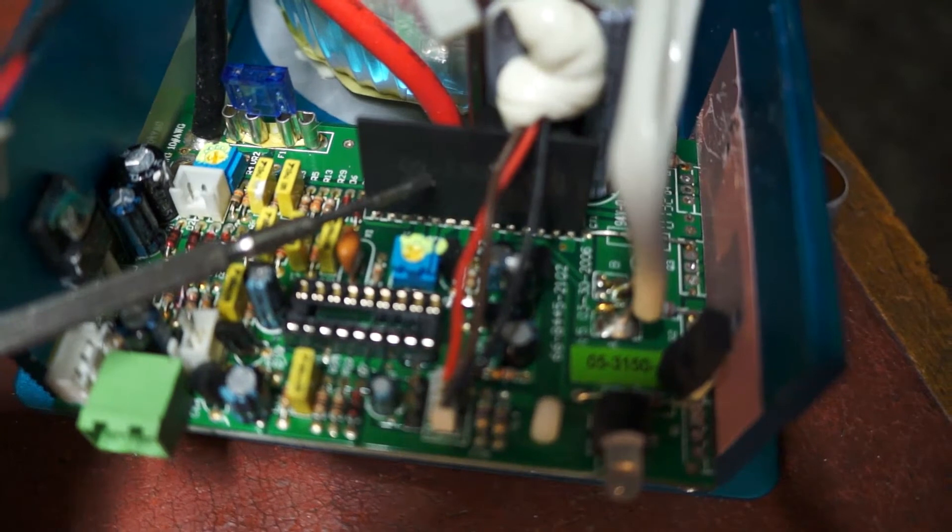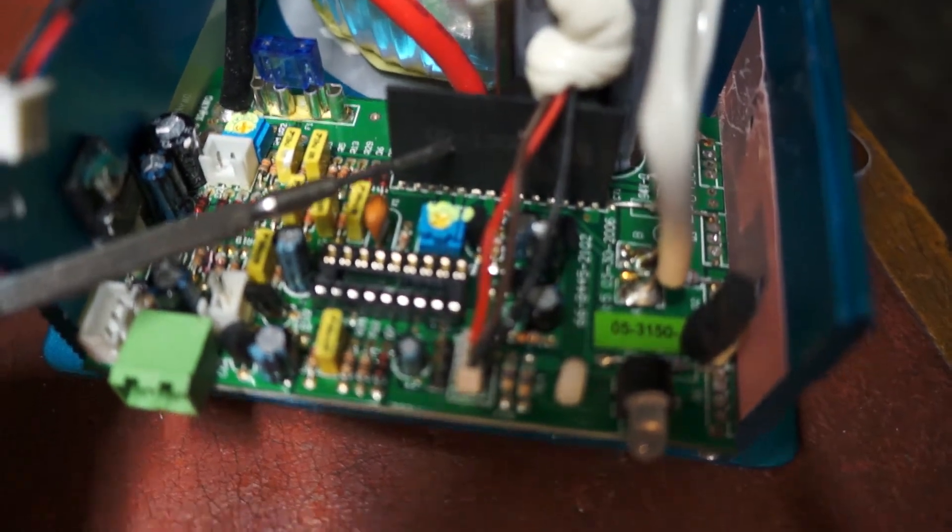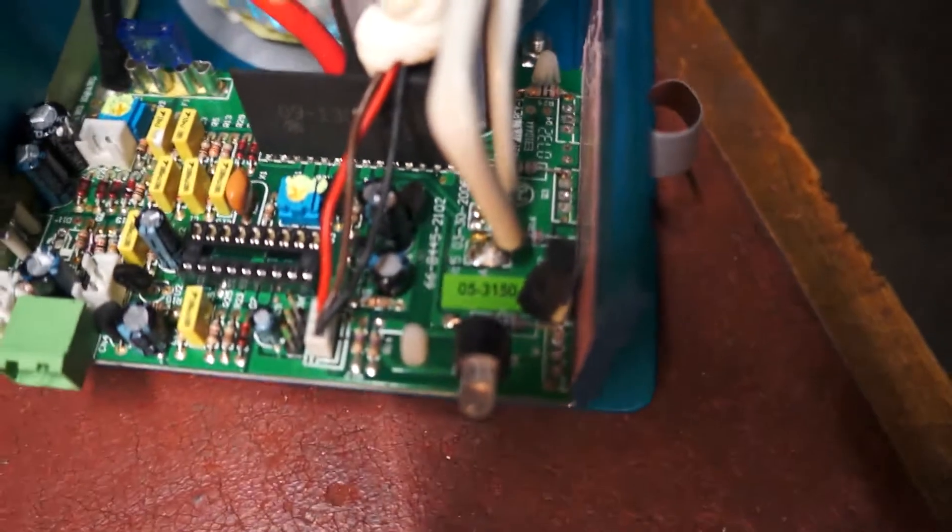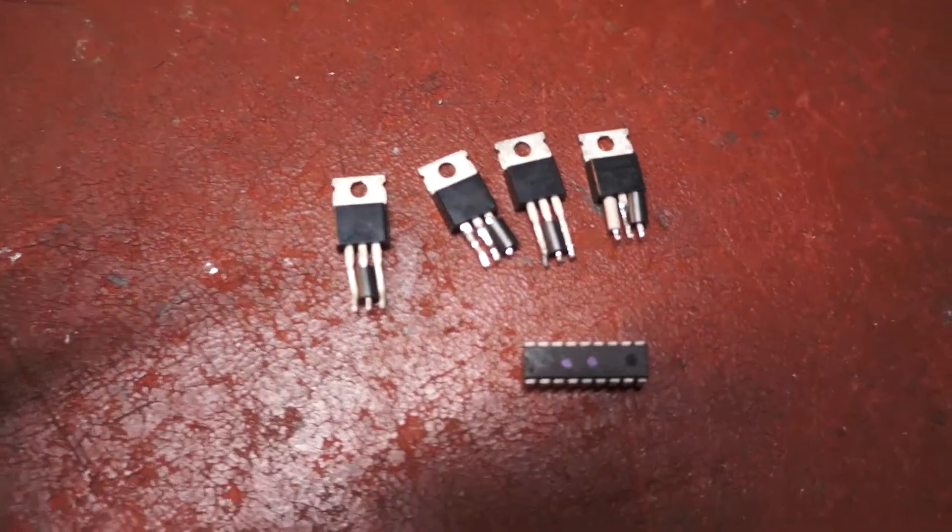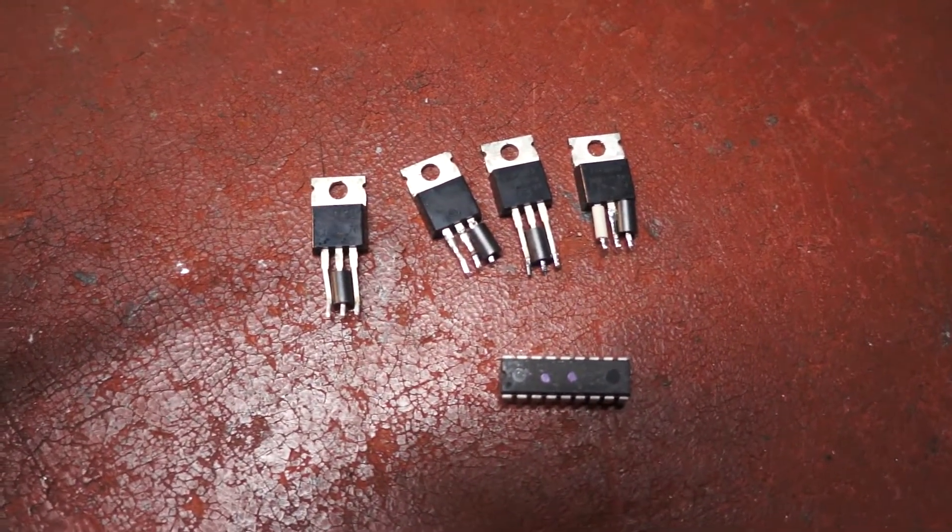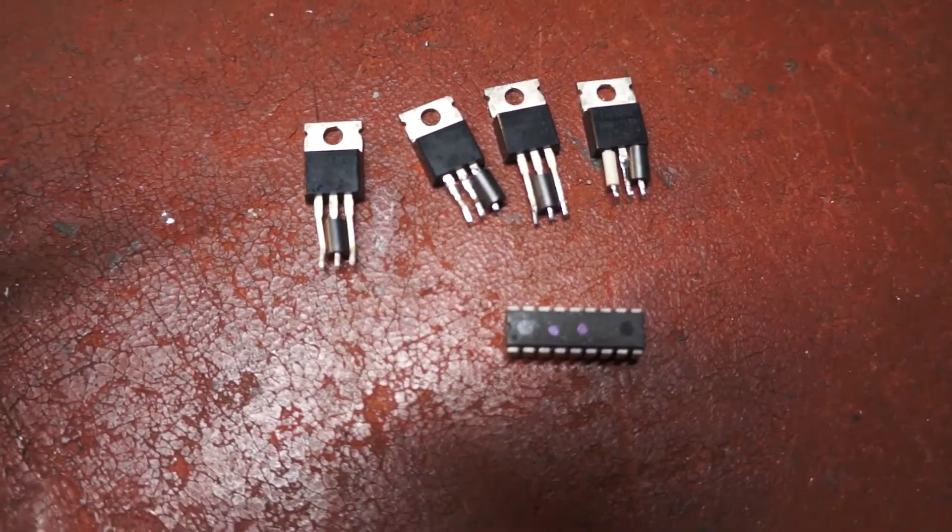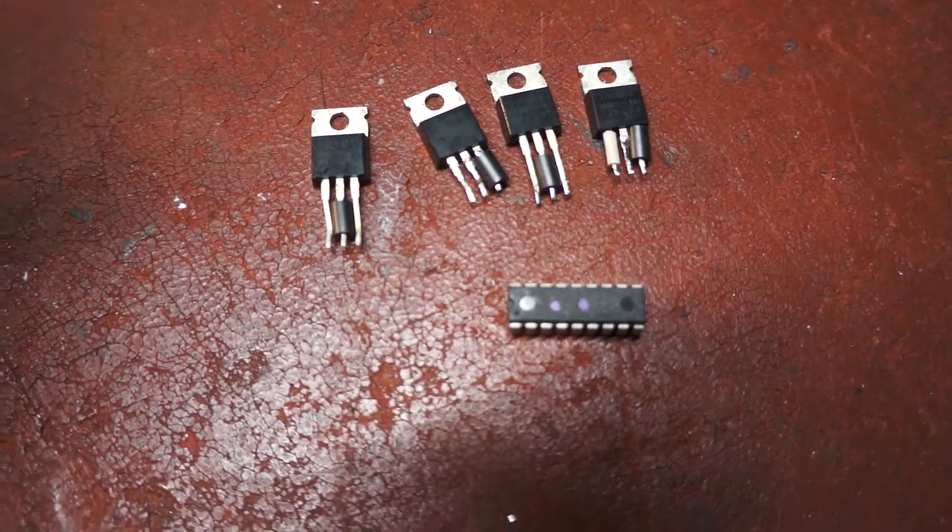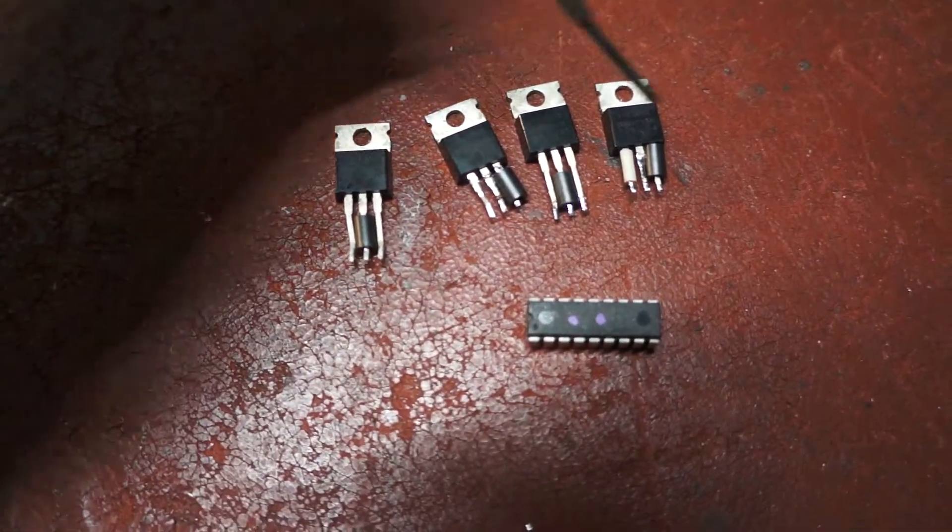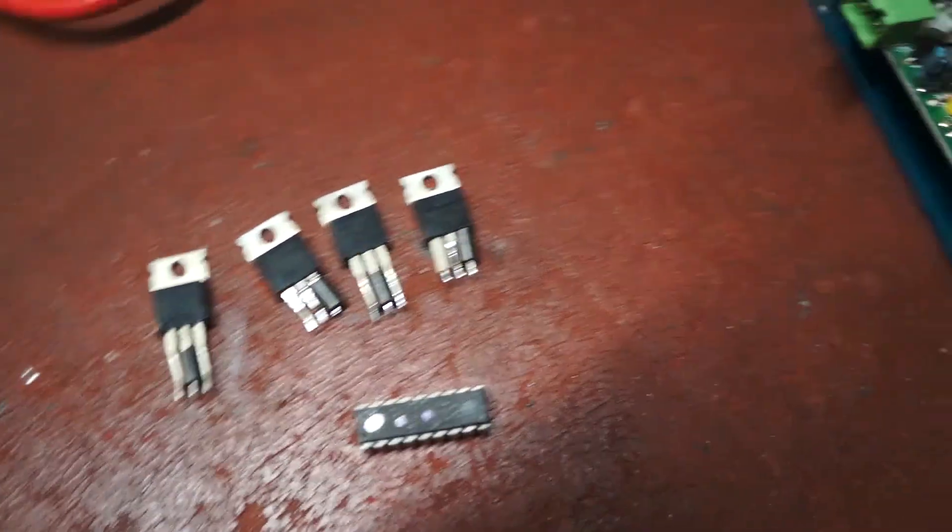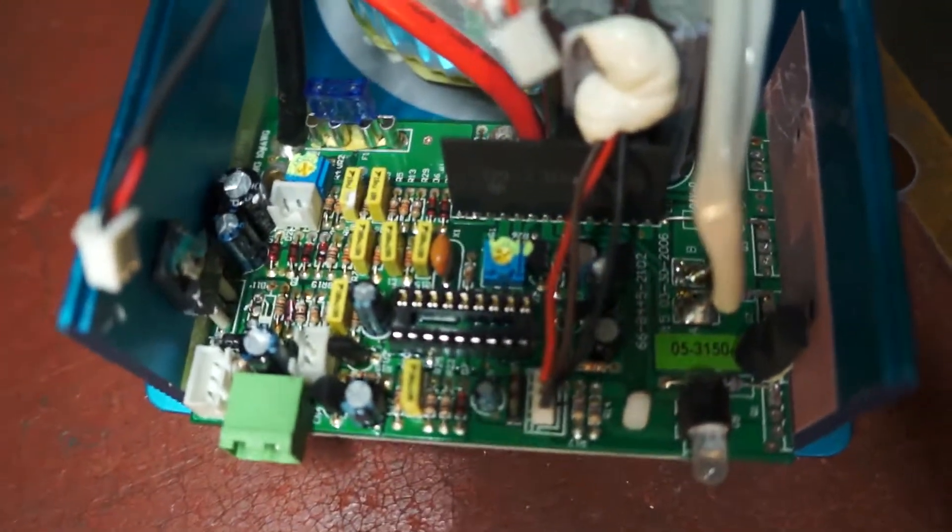It appears to me that this thick film IC here has a defect in it, because looking at the four outputs that drive the MOSFETs, I found that one of them was low in voltage. So presumably the drive to the MOSFETs was not as it should be.